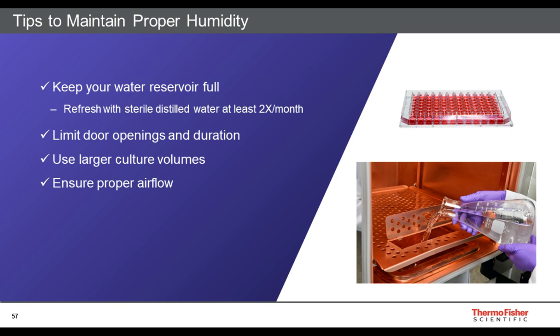Just like with temperature and carbon dioxide, if you're trying to maintain an artificial environment inside the incubator that's very different than the conditions in the surrounding laboratory, limit the door openings and duration. And this is especially important in a clean room where you may have the ambient temperature in the laboratory much lower than in the incubator. So normal room temperature for many of us is between 20 and 22 degrees Celsius. But in a clean room, if you're wearing a Tyvek suit, of course, that gets very warm, and so many clean rooms are set at 16 degrees Celsius, and they're drier than the incubator or even than a typical laboratory, which is about 50% humidity. So that increases the difference between the ambient laboratory and the incubator when you're in a clean room.